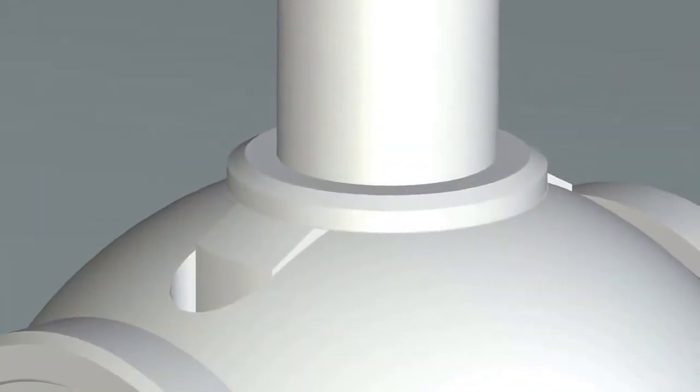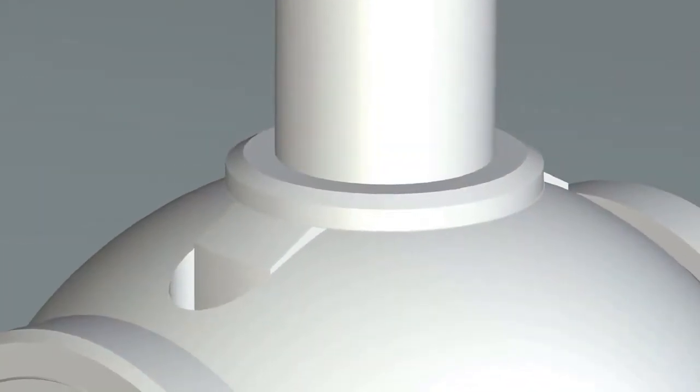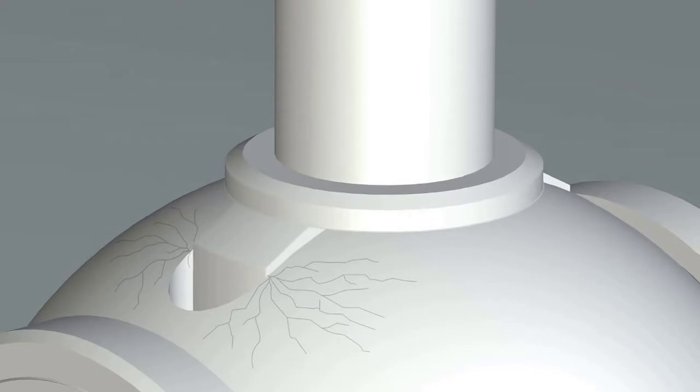However, in rare instances, the plastic-to-plastic joint between ball and stem can lead to play between the stem and the shaft. When the medium is under pressure, the torque can increase, sometimes resulting in the outer edges of the liner in the slot of the ball being heavily loaded. With intensive use, these may become worn.